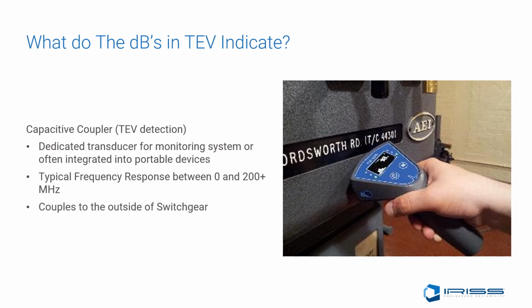TEV anomalies are a very convenient phenomenon for measuring and detecting partial discharge as they can be detected without making an electrical connection or removing any panels. While this method may be useful to detect some issues in switchgear and surface tracking on internal components, the sensitivity is not likely to be sufficient to detect issues within solid dielectric cables.